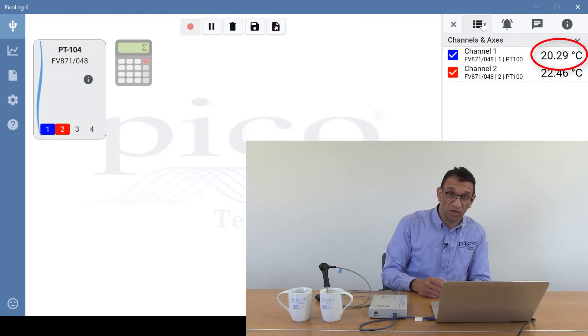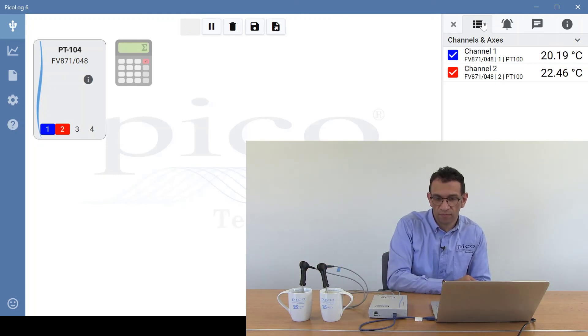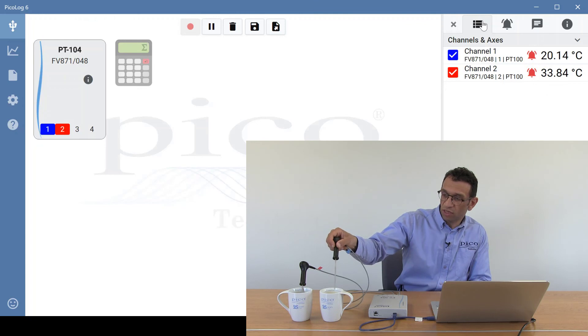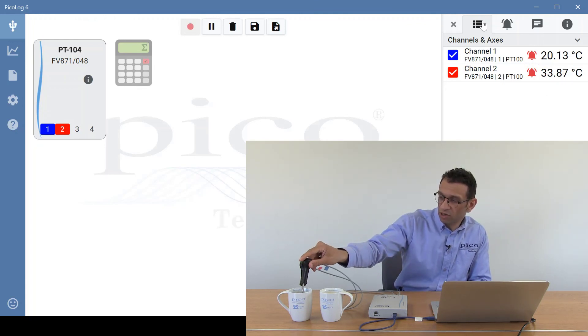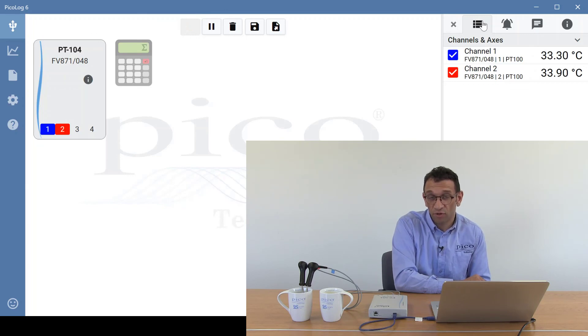Clicking save and going to channel axis, we put channel one in the cold mug. As you can see, channel one is below 21 degrees Celsius but it isn't alarming because channel two also has to be above 30. Putting the second probe in the second mug, you can see it now alarms. Just to prove it, taking the channel one probe out and putting it into the second mug, you can see it isn't alarming — proving that the boolean expression works.